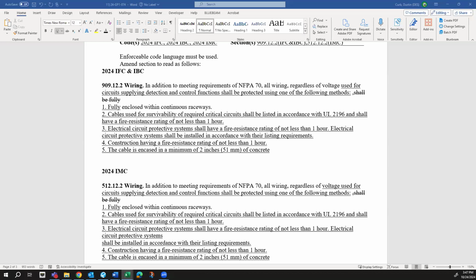But I just think that this could be interpreted that we would potentially lessen the requirements of the continuous raceways. I'm not opposed to it if you have, for example, a dedicated shaft enclosure for the wiring, that would provide the same level of protection as the continuous raceways. I agree with that. But my example of running open cable in a 1 hour stacked electrical room was basically my concern, that somebody could interpret that and not provide the continuous raceways when the cables are inside that 1 hour stacked electrical room.